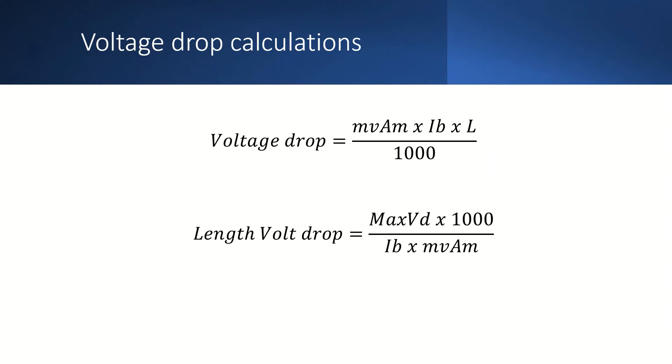Then divide by the design current and divide by the value for millivolts per ampere per meter for the cable. That will give us the maximum circuit length to comply with the volt drop.